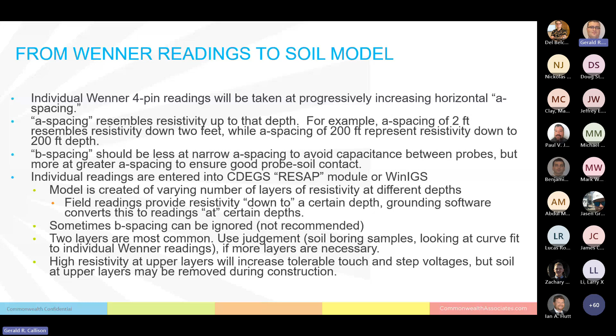Now you have to use your judgment, looking at the soil boring samples, looking at curve fittings to individual Wenner readings to determine if more layers are necessary. And we're going to talk a lot about that judgment down the road in this presentation. Another thing to be careful of, of course, is that high resistivity at upper layers is going to increase tolerable touch and step voltages, but soil at upper layers might be removed during construction. So use some judgment as to how you account for those upper layers.